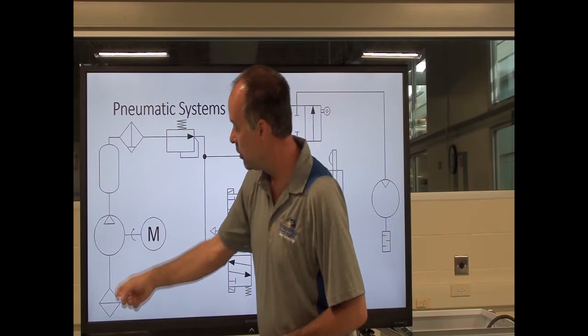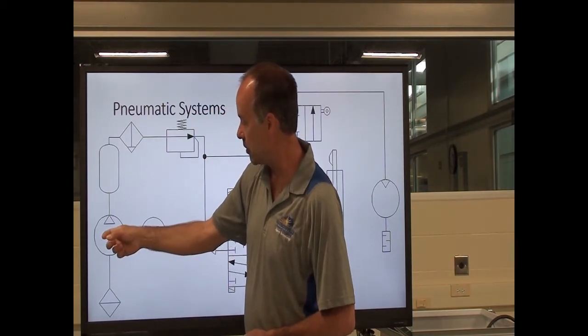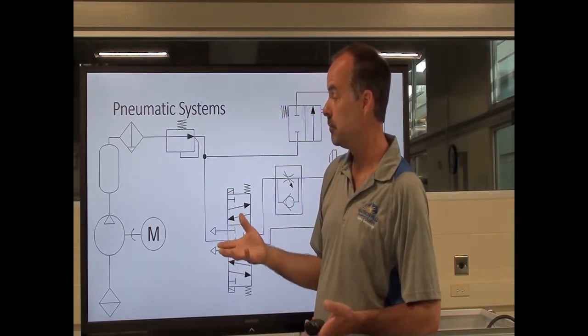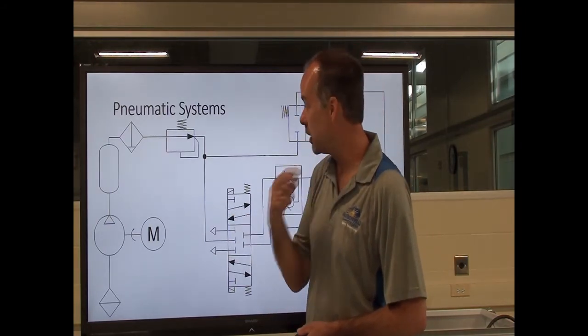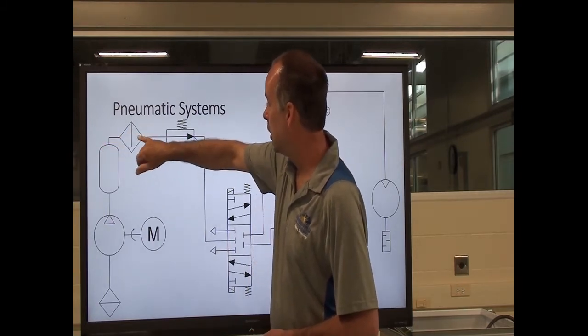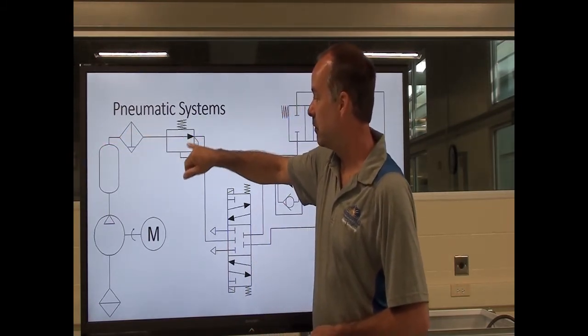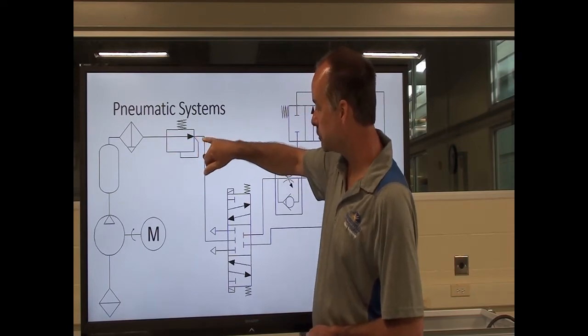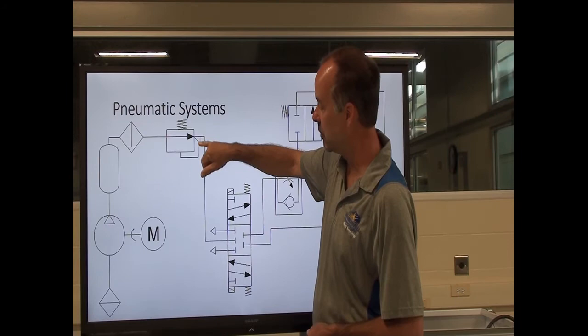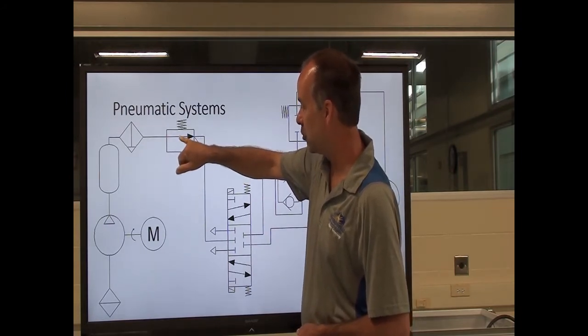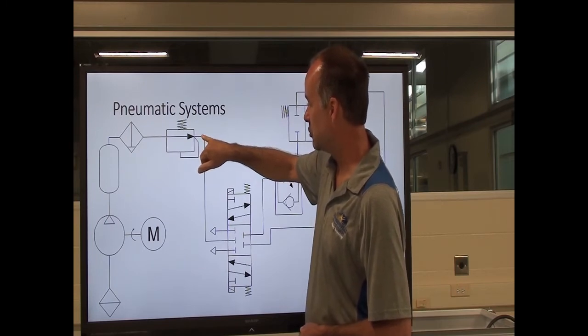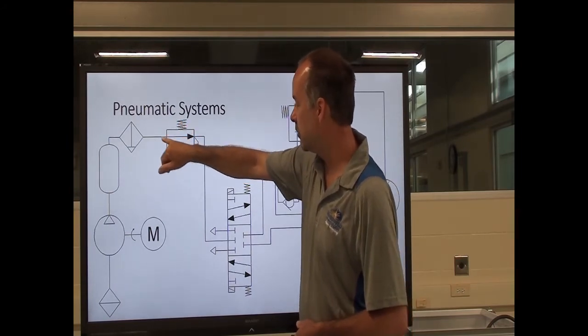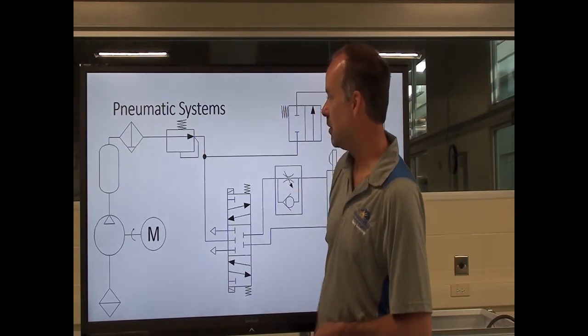Air is drawn in through a filter and compressed. The first thing I come to is a pneumatic receiver, which is a large holding tank. Coming out of my receiver, I go through another filter. Then instead of a relief valve, I go to a pressure reducing valve. I know this is a pressure reducing valve because it's normally open, and my pilot port is on the outlet side of the valve acting on the spool against the spring. When my outlet pressure reaches the set level, this shifts the spool out of the flow path, stopping flow to maintain pressure on the outlet side.